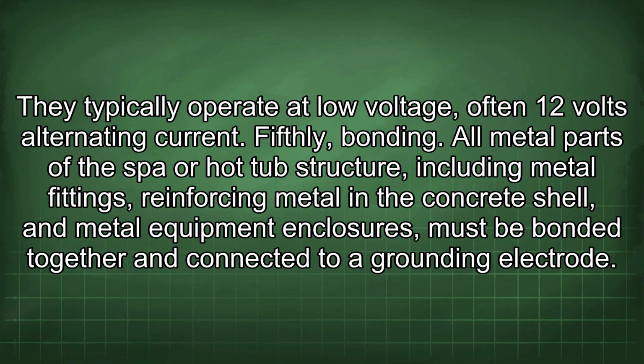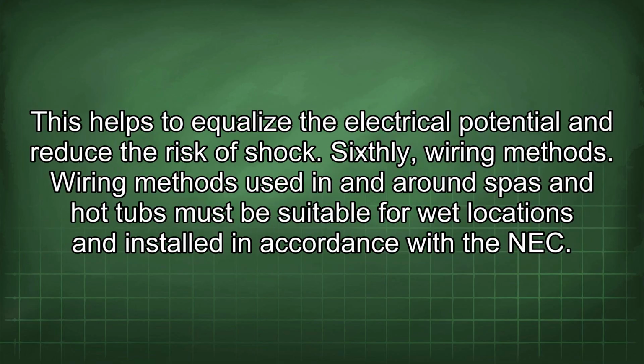They typically operate at low voltage, often 12 volts alternating current. Fifthly, bonding. All metal parts of the spa or hot tub structure, including metal fittings, reinforcing metal in the concrete shell, and metal equipment enclosures, must be bonded together and connected to a grounding electrode. This helps to equalize the electrical potential and reduce the risk of shock. Sixthly, wiring methods. Wiring methods used in and around spas and hot tubs must be suitable for wet locations and installed in accordance with the NEC.